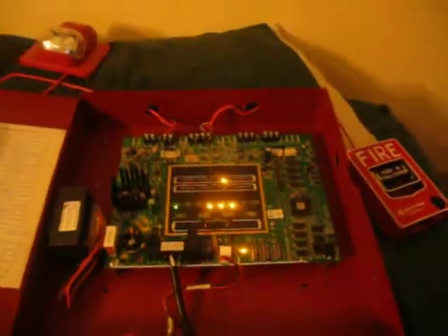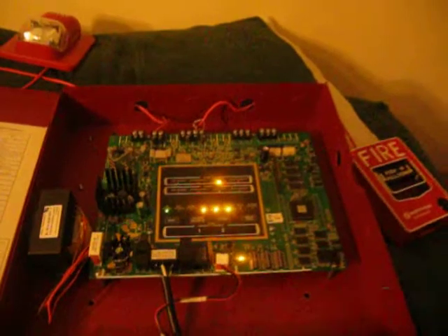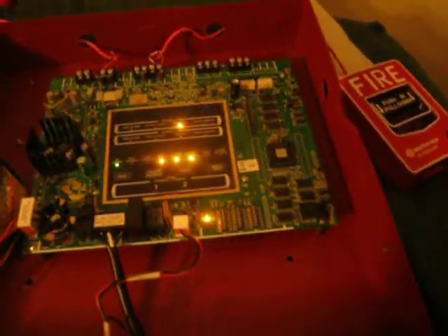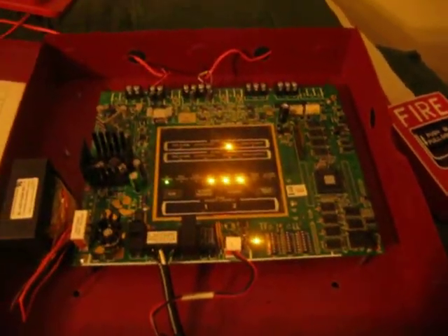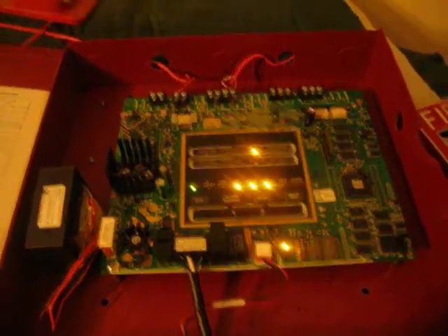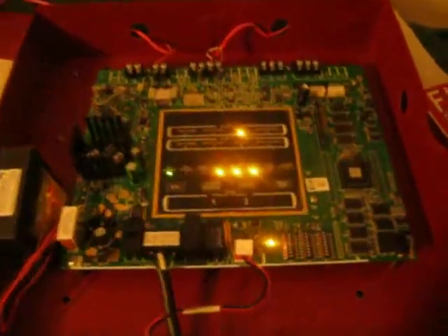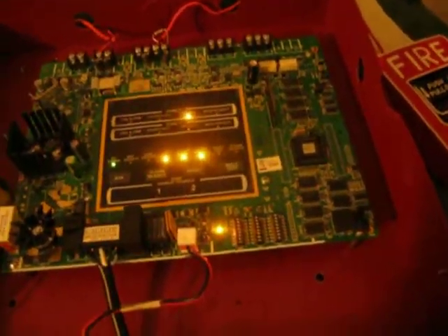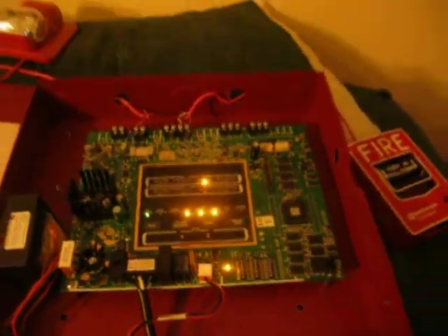Okay, as you can see here, I have a couple of troubles here showing a NAC fault, probably because I don't have a resistor. And I got a trouble with Zone 1 because I do not have a resistor.